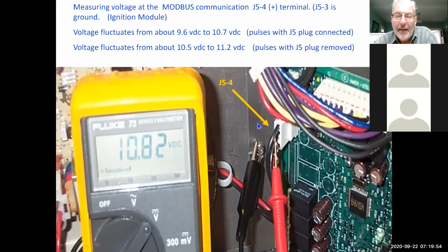Okay, and that applies to the older stuff and the newer stuff. So if you're working on the old Voyagers or the new Voyagers, these voltages are the same. It applies to stuff going back to around 1990, 92, somewhere in there. Now on the newer stuff on the ReliaTel, there's a couple different voltages that we need to look for. There's some reference voltage. And what we're doing on the ReliaTel stuff is we're using what's called Modbus communication. And the Modbus communication on J5.4, and J5.3 is ground.